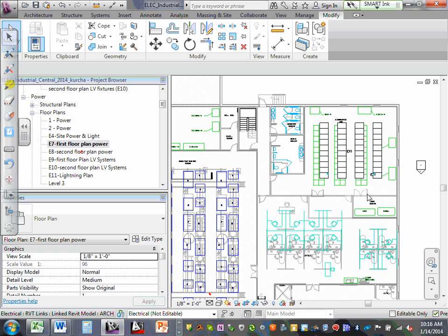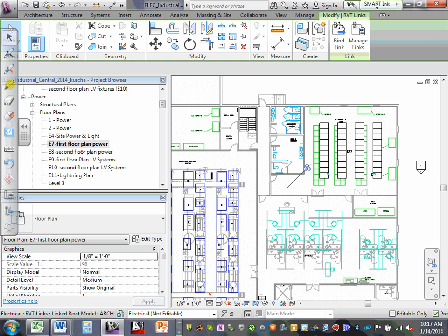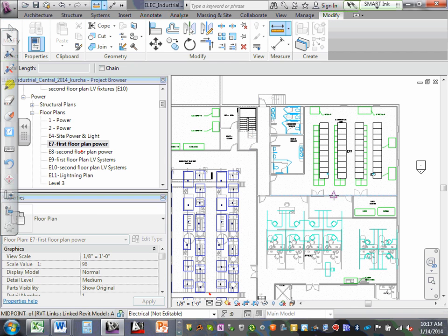And if you have one of these templates, this is the tool to use. I don't know if everybody's seen one of these. These boxes are great. You just lay them on your 1/8" scale drawing. It'll tell you what candela rating strobe to use based on the square footage that you're dealing with. Okay. So what I do is I'll come in 25 feet from the wall. What is the distance between this wall and this wall? 40 feet.